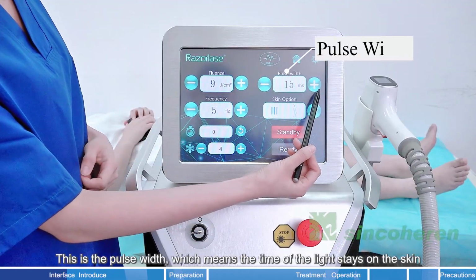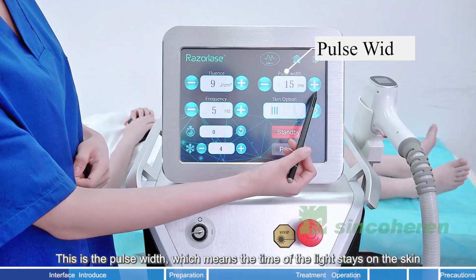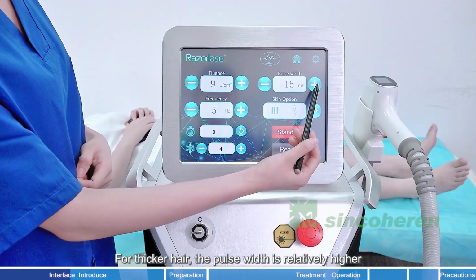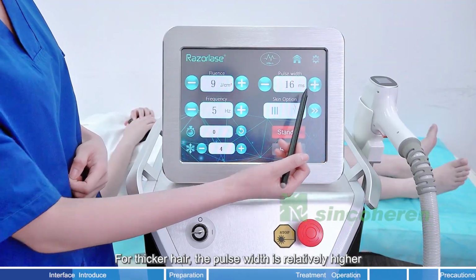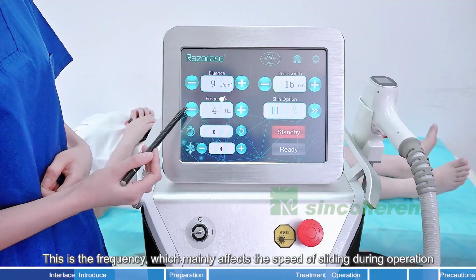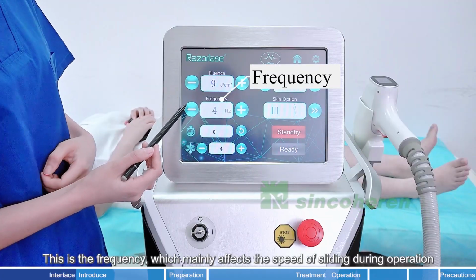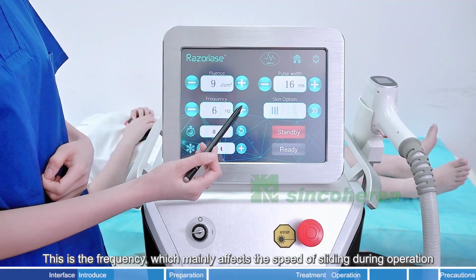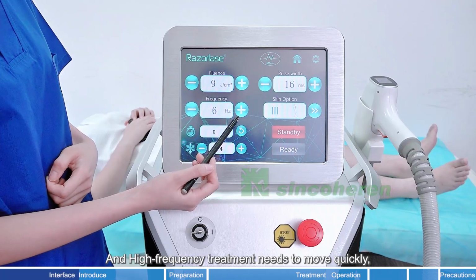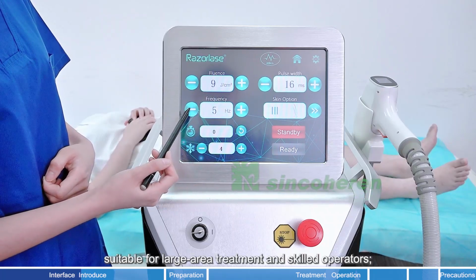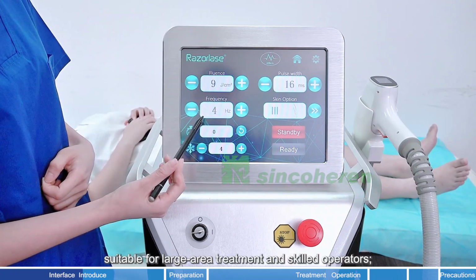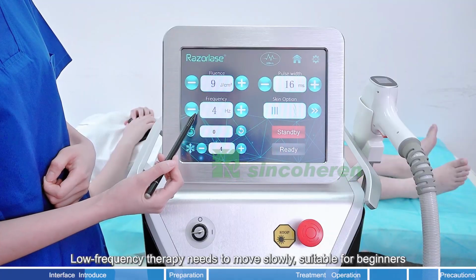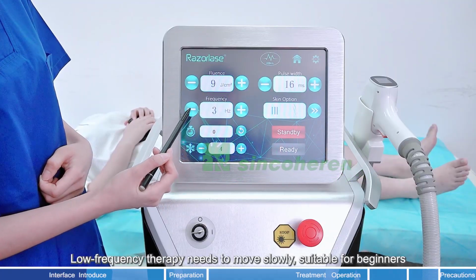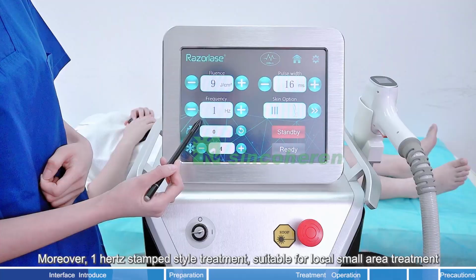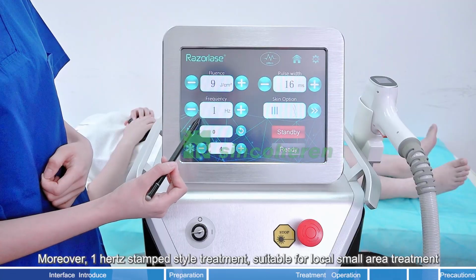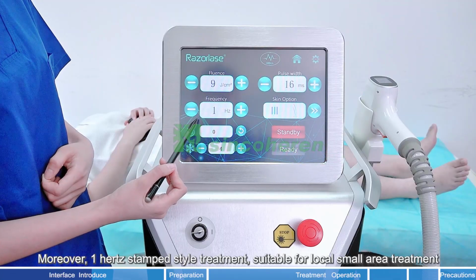This is the pulse width, which means the time the light stays on the skin. For thicker hair, the pulse width is relatively higher. This is the frequency, which mainly affects the speed of sliding during operation. High frequency treatment needs to move quickly, suitable for large area treatment and skilled operators. Low frequency therapy needs to move slowly, suitable for beginners. Moreover, 1 Hz stamp style treatment is suitable for local small area treatment.